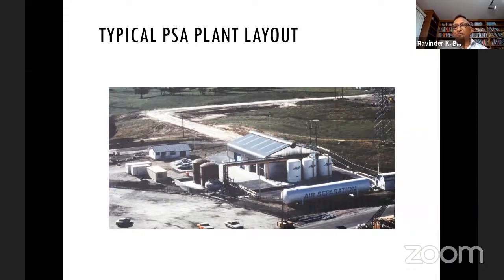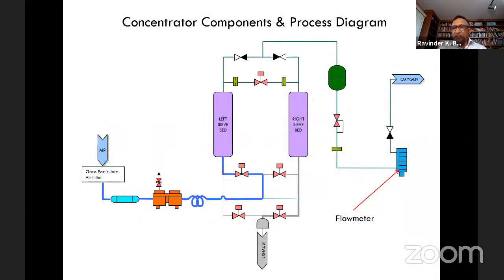So PSA plants go from portable concentrators to field installations like this. For a concentrator, the kind used at home, we eliminated the second valve because these beds are very small. We can depressurize them reasonably with one bed and one valve in a reasonable time. We're also able to combine the purge, equalization, and oxygen repressurization functions in one valve. The cycle stays the same, but we can use one valve.